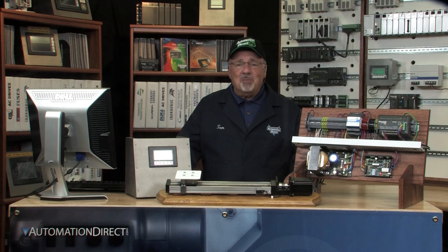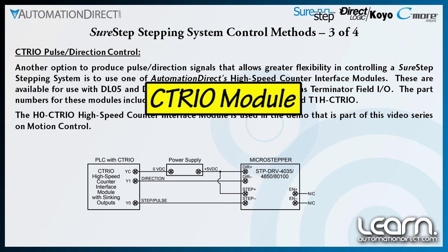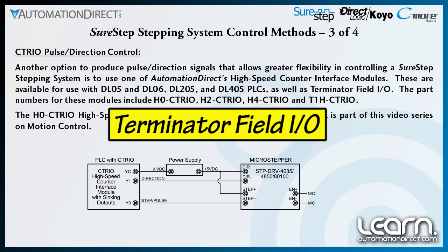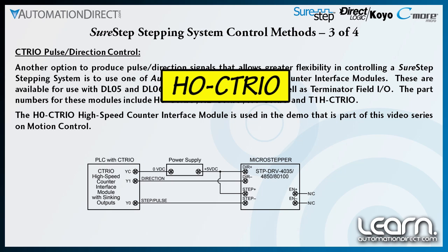The next control method can also provide pulse and directional signals to a SureStep stepping system. This is done by using one of AutomationDirect's high speed counter interface modules, commonly referred to as a C-TRIO module. The C-TRIO module is available for use with the DL05, DL06, DL205, and DL405 families of PLCs, as well as AutomationDirect's Terminator field IO. Using a C-TRIO module allows more flexibility and higher speeds over the built-in high speed pulse output feature. I have chosen to use the H0-C-TRIO high speed counter interface module installed in a DL05 PLC as the control method for my demonstration application.